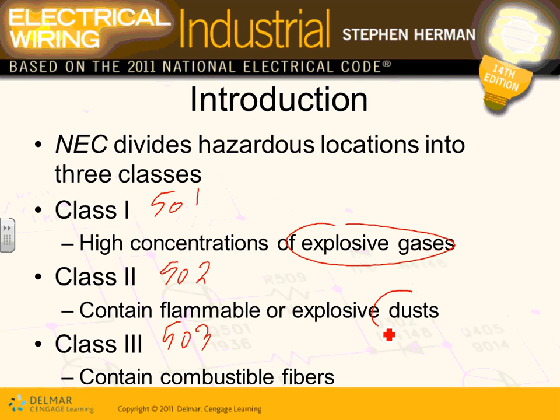Class 2 is dust. Flammable dust. Any location where you have a cloud of dust that's flammable and could ignite and explode. This is called explosive dust, or flammable or explosive dust. That's called Class 2 dust locations.